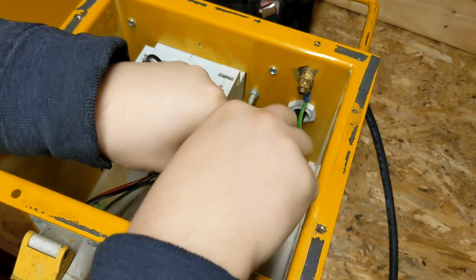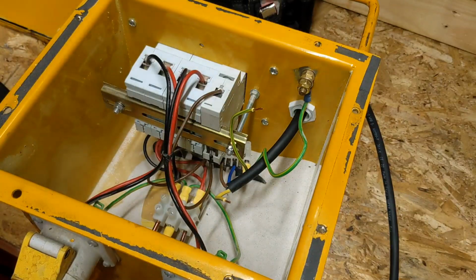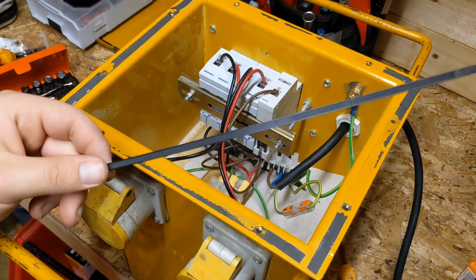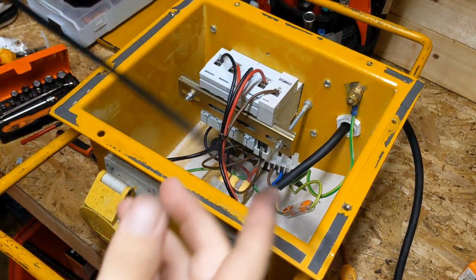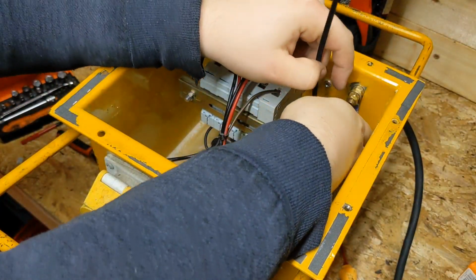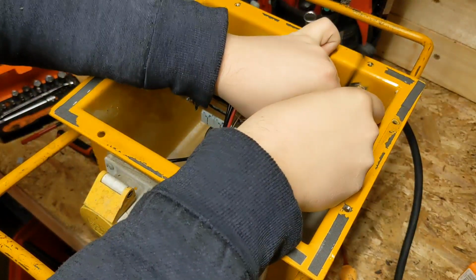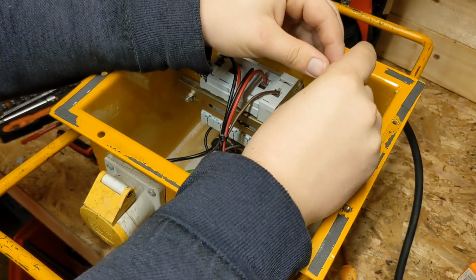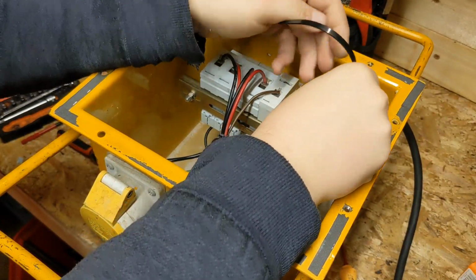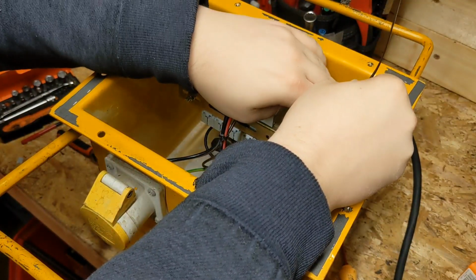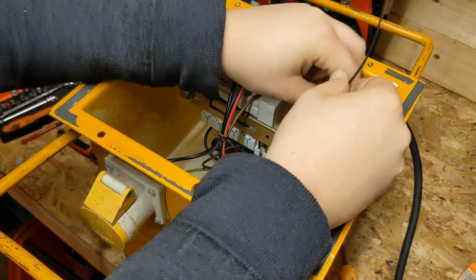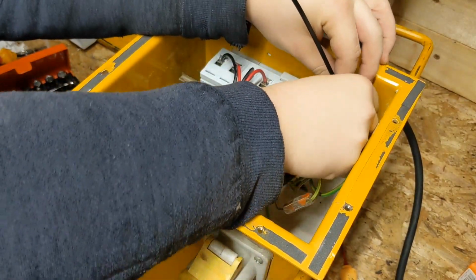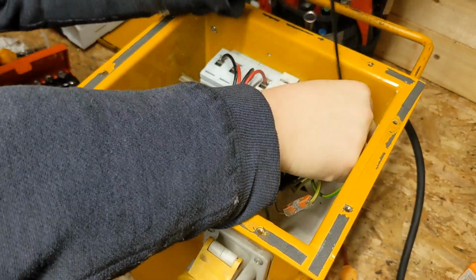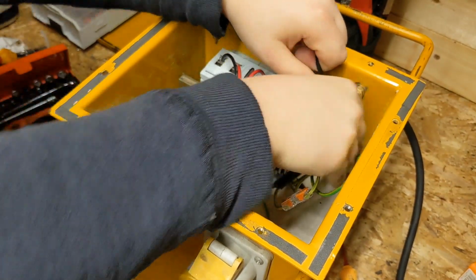And we'll use a Wago. Right, first thing we're going to do is grab a cable tie and push it around the wire like this, then pull it tight. Basically what this does is add an extra layer of strain protection, because in stuffing glands, if you pull hard enough, you can actually pull wires out of them.